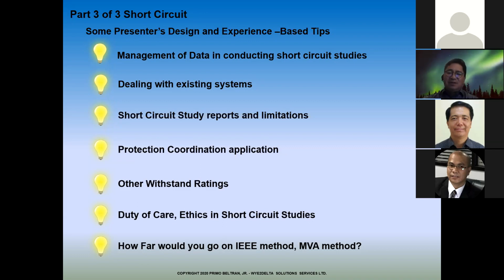In the MVA method, everything else is the same - it takes the locked rotor current, it takes the contribution, but it's not able to separate R and X. And in the MVA method, they use a fixed X over R equivalent to 14, not 17, not 6.59, not 1.73 - which is lower than those. So we have to be careful.